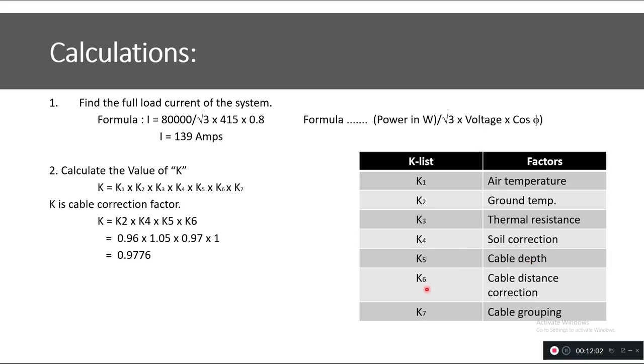K1 is the air temperature factor, K2 is ground temperature, K3 is thermal resistivity of the soil, K4 is soil correction, K5 is cable depth, K6 is cable distance correction, and K7 is cable grouping. Since I am laying the cable underground, I will not consider K1. I will also not consider K3 since I don't know the soil's thermal resistivity — instead I will use the soil correction factor K4 for damp soil. I will consider K5 for 1 m depth. Since there are no existing cables and only one cable run, K6 and K7 are taken as 1.